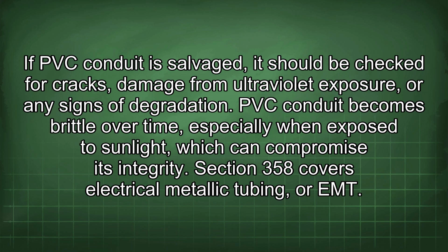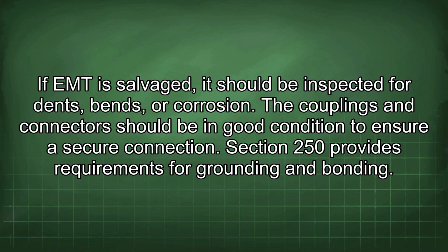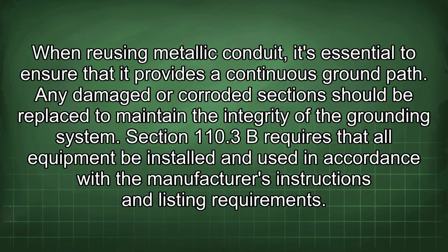Section 358 covers electrical metallic tubing, or EMT. If EMT is salvaged, it should be inspected for dents, bends, or corrosion. The couplings and connectors should be in good condition to ensure a secure connection. Section 250 provides requirements for grounding and bonding. When reusing metallic conduit, it's essential to ensure that it provides a continuous ground path. Any damaged or corroded sections should be replaced to maintain the integrity of the grounding system.